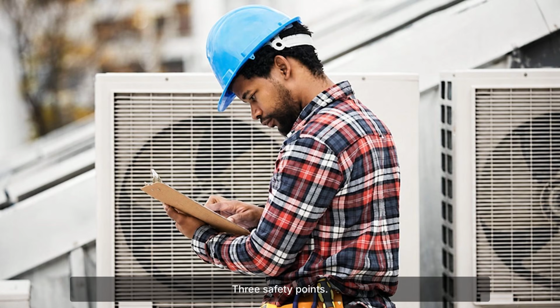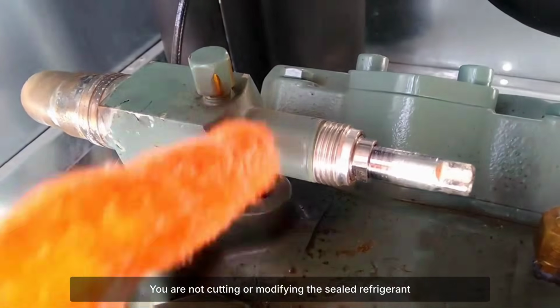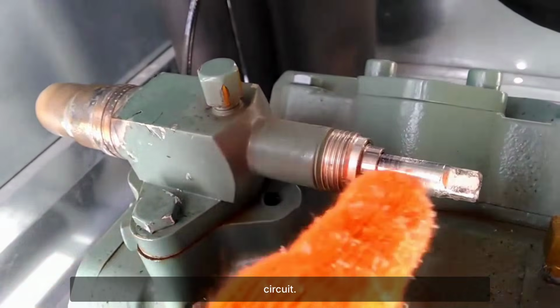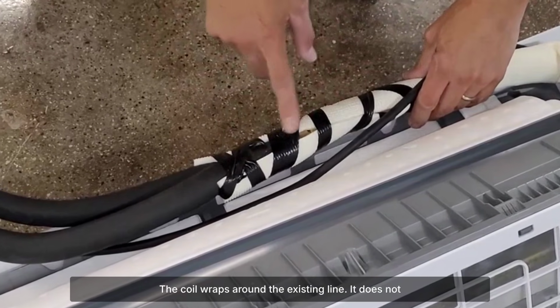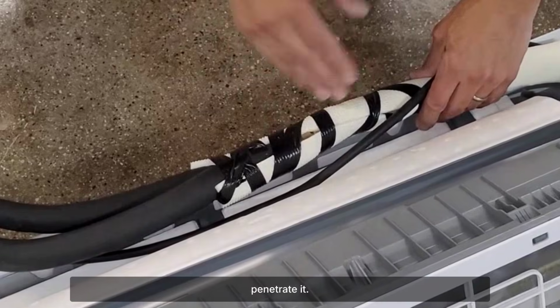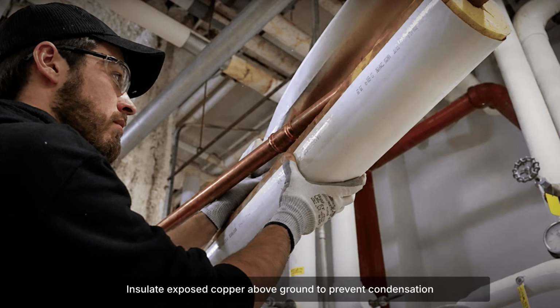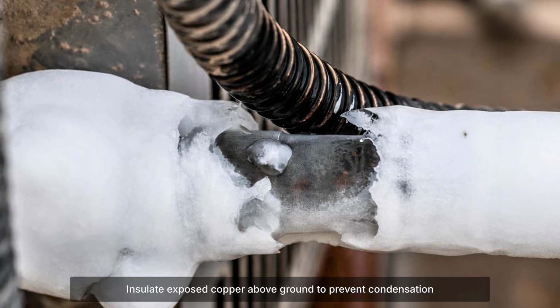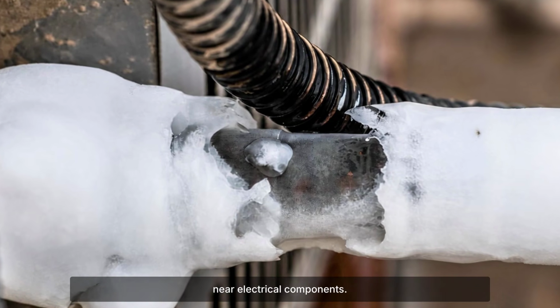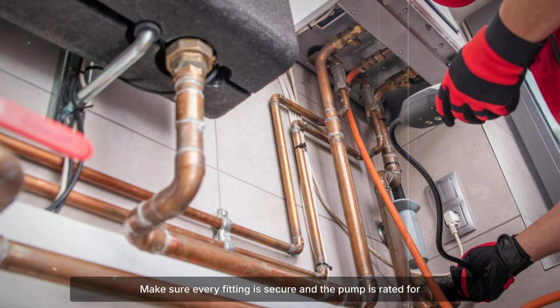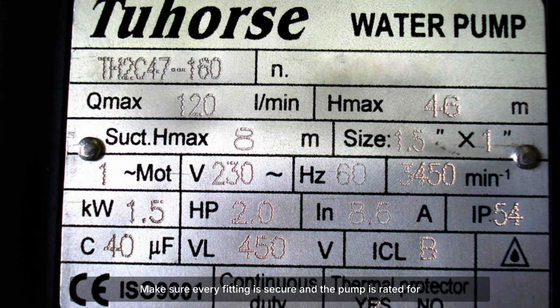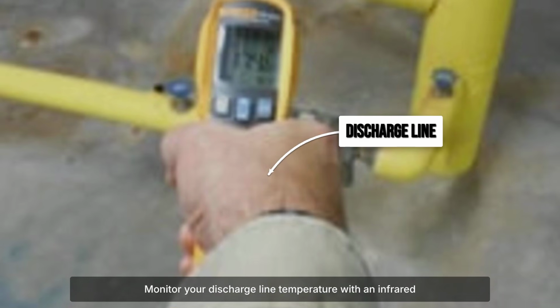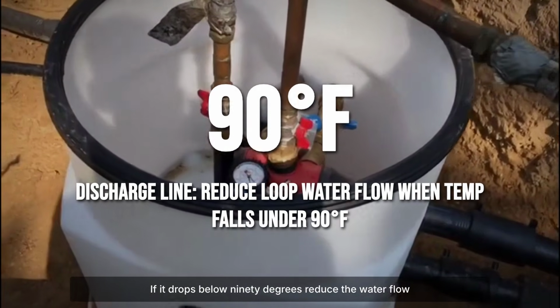3 safety points. You are not cutting or modifying the sealed refrigerant circuit. The coil wraps around the existing line. It does not penetrate it. Insulate exposed copper above ground to prevent condensation near electrical components. Make sure every fitting is secure and the pump is rated for continuous operation. Monitor your discharge line temperature with an infrared thermometer. If it drops below 90 degrees, reduce the water flow immediately.